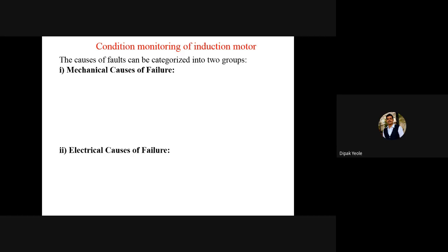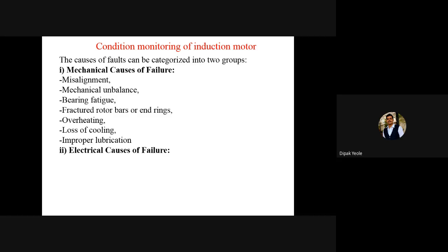What are the mechanical causes? They are related to misalignment, mechanical unbalance, bearing fatigue. The bearings can get into a failure state condition, fractured rotor bars or end rings, overheating, loss of cooling so the fan inside the induction motor gets damaged, and improper lubrication. These fall under the category of mechanical causes.